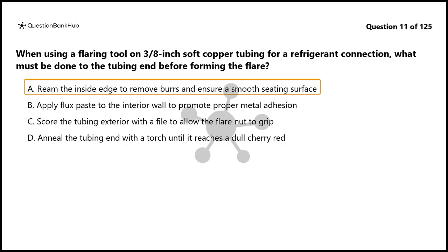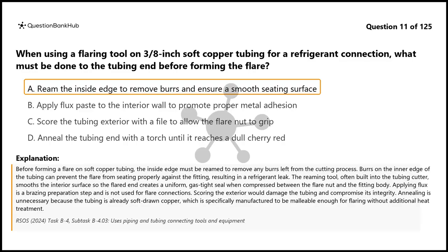The correct answer is A. Before forming a flare on soft copper tubing, the inside edge must be reamed to remove any burrs left from the cutting process. Burrs on the inner edge of the tubing can prevent the flare from seating properly against the fitting, resulting in a refrigerant leak. The reaming tool, often built into the tubing cutter, smooths the interior surface so the flared end creates a uniform, gas-tight seal when compressed between the flare nut and the fitting body.